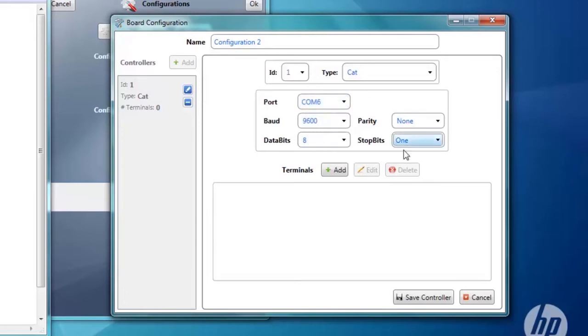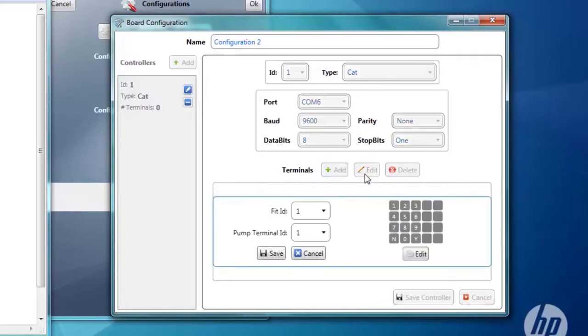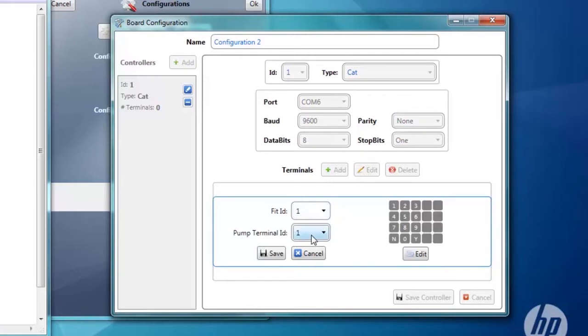Now it's time to add a terminal. Select a new terminal and click Edit. Our FIDID is 1, pump terminal ID is 1. The FIDID is an address that the FSC3000 uses, and the pump terminal ID is an address that is set up on the terminal at the pump.